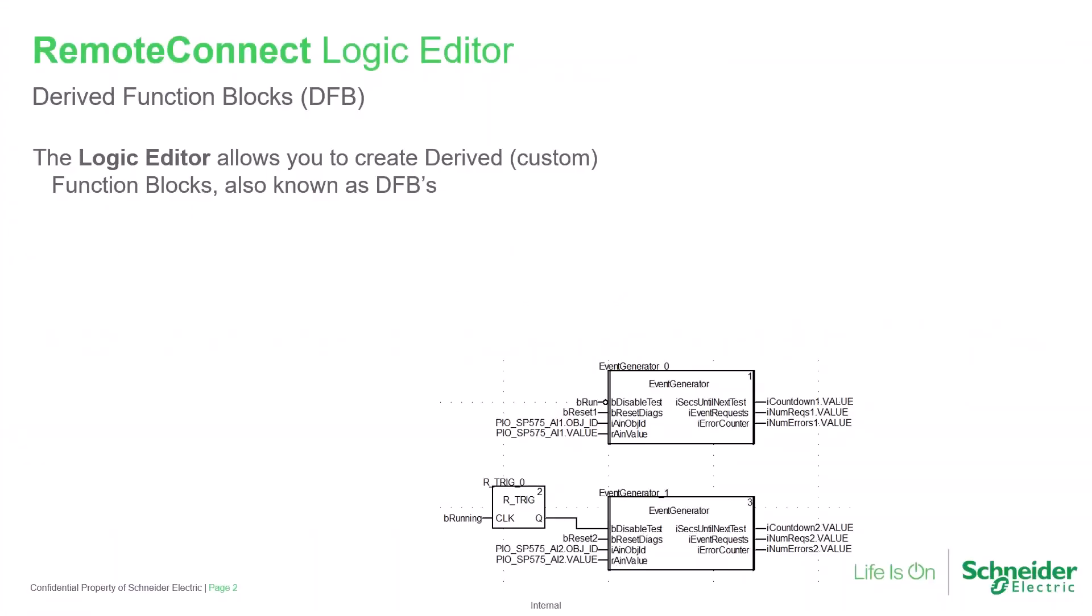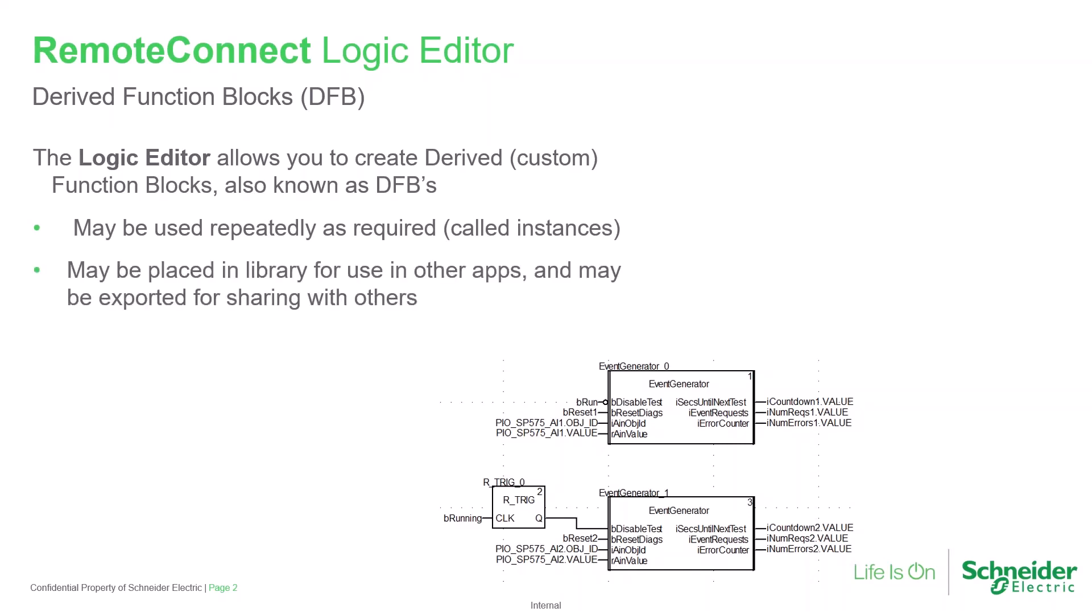When using RemoteConnect with an X70 type ScadaPack, the logic editor provides the ability to create derived or custom function blocks, also known as DFBs. These can be repeatedly used wherever desired in an application. Each usage is called an instance. They may be placed into a library for use on other projects, and they can be shared with others as well.